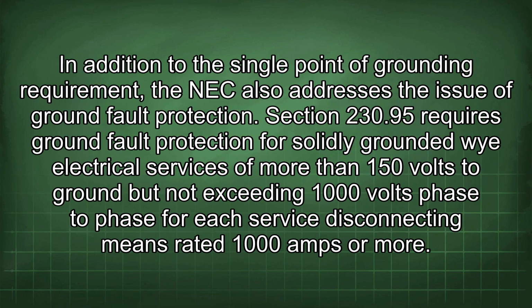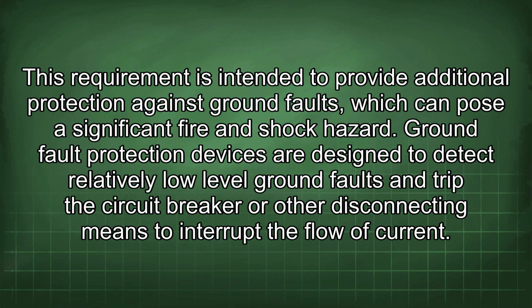In addition to the single point of grounding requirement, the NEC also addresses the issue of ground fault protection. Section 230.95 requires ground fault protection for solidly grounded wye electrical services of more than 150 volts to ground, but not exceeding 1000 volts phase to phase for each service disconnecting means rated 1000 amps or more. This requirement is intended to provide additional protection against ground faults, which can pose a significant fire and shock hazard. Ground fault protection devices are designed to detect relatively low-level ground faults and trip the circuit breaker or other disconnecting means to interrupt the flow of current.